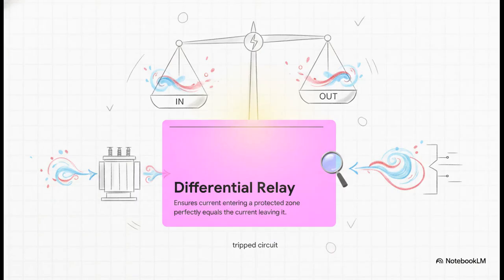I always like to think of the differential relay as an incredibly strict accountant, but one that operates at the speed of light. Its whole existence boils down to one simple rule: what goes in must perfectly equal what comes out. If the current entering the transformer's protected zone doesn't perfectly match the current leaving it, the relay instantly knows, uh-oh, current is leaking somewhere inside that tank.